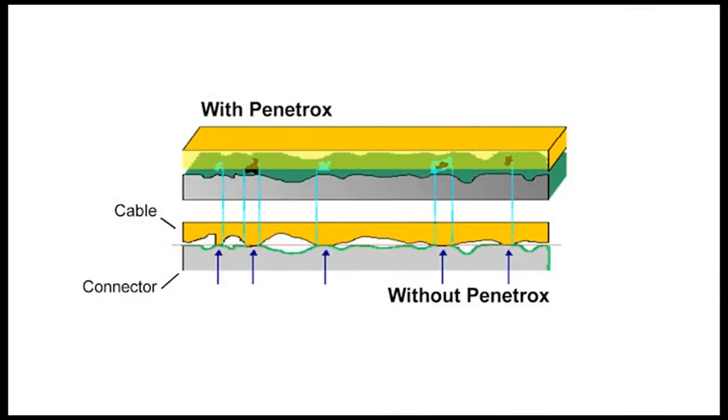This is what you would see if we had the connection cross section under a microscope. You can see that not everything is perfectly matched up for contact points. But now we put the penetrox in there. That fills in all these little gaps. That's what you're gaining by having that penetrox E in every type of compression ground connector.